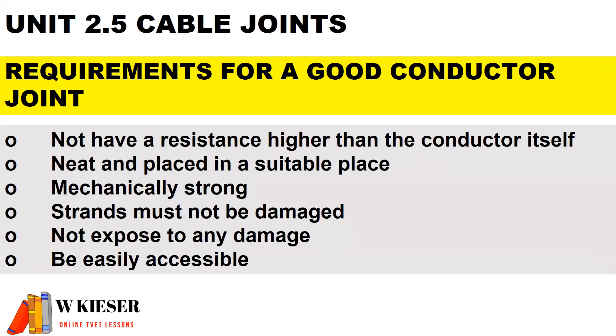The requirements for a good conductor joint: the joint should not have a higher resistance than the conductor itself. It must be neat and placed in a suitable place, mechanically strong, and the strands must not be damaged. It should not be exposed to any damage, and it must be easily accessible.